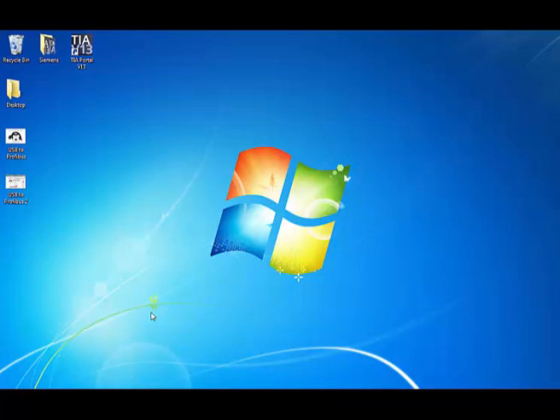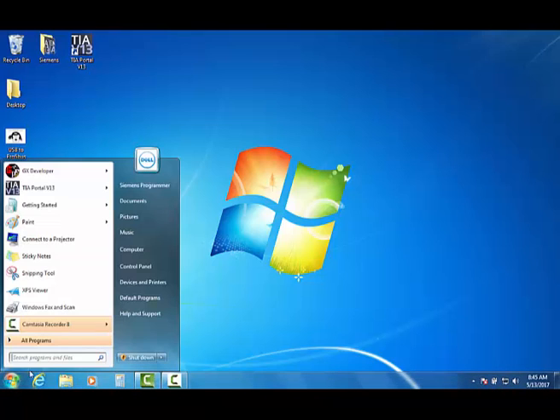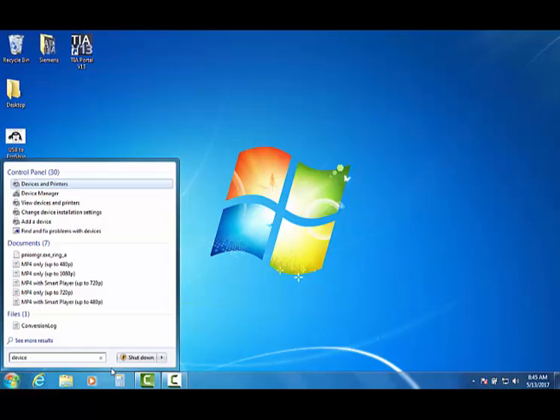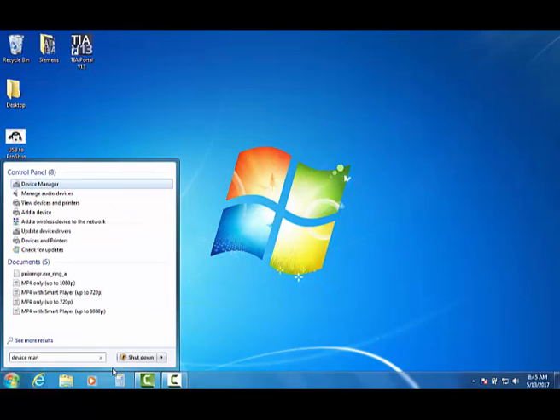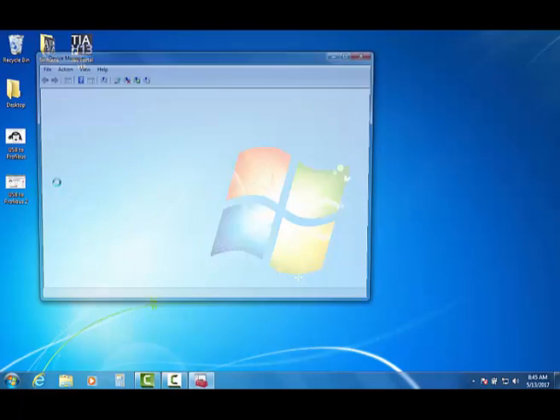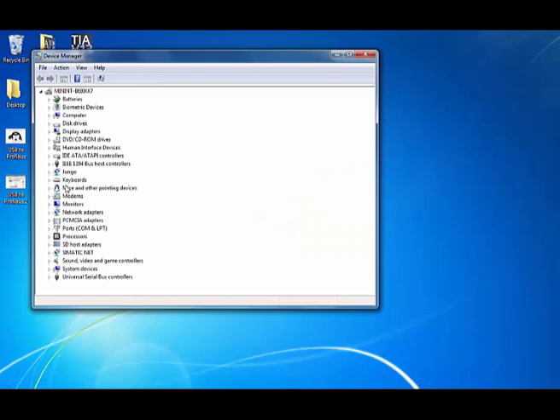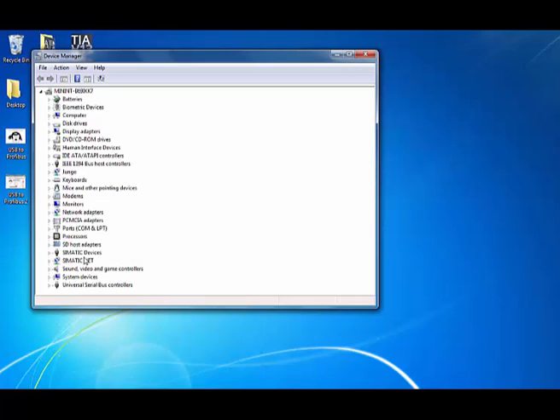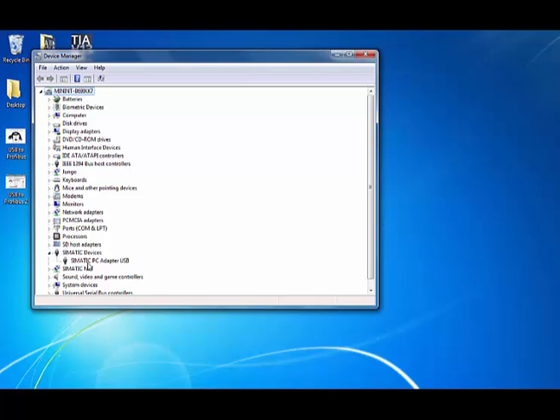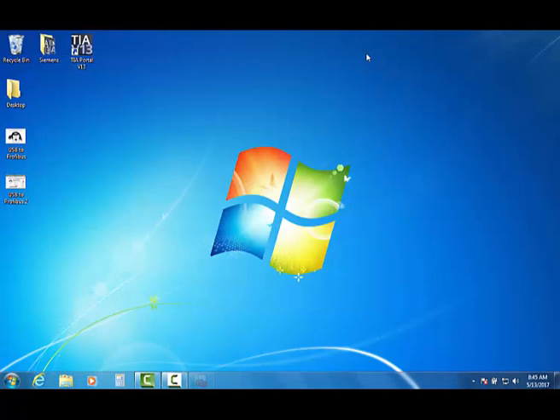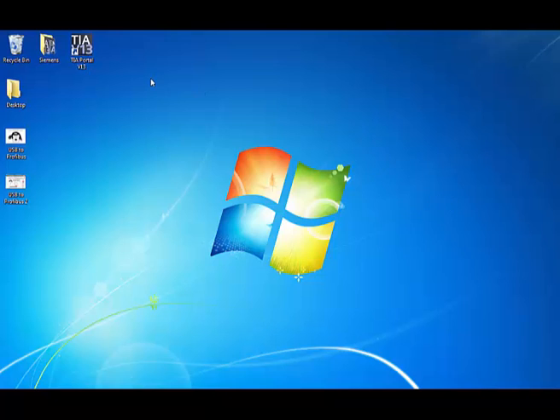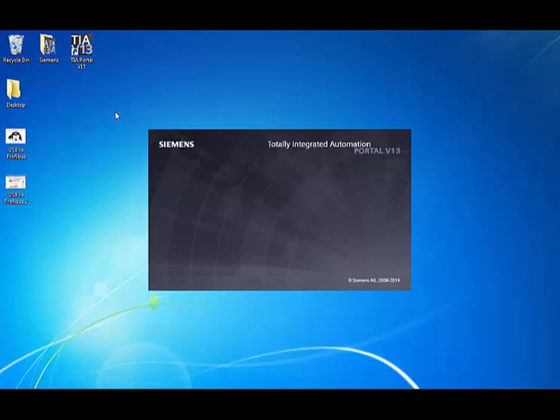Let's first start out opening it in Device Manager. We're using Windows 7 Professional along with TIA Portal Professional. Just above SIMATIC NET, you'll see after we plug the cable in, it'll load the drivers. And it shows up SIMATIC devices, SIMATIC PC adapter USB. If you have an asterisk next to this, then you're going to have to reload part of your Profibus, the TIA Portal software, just so the drivers are actually fully loaded.